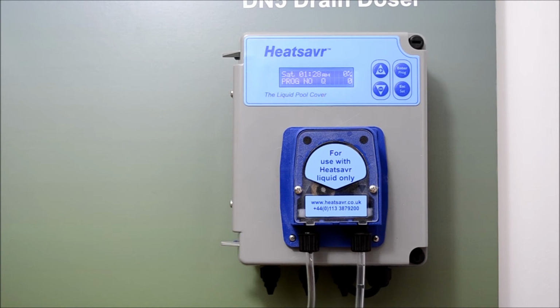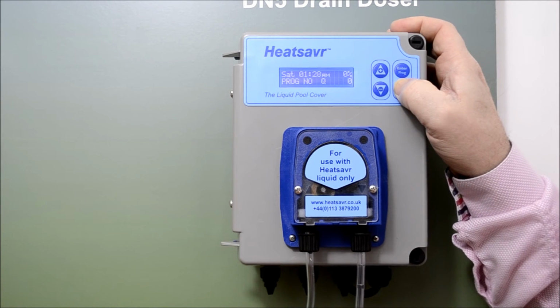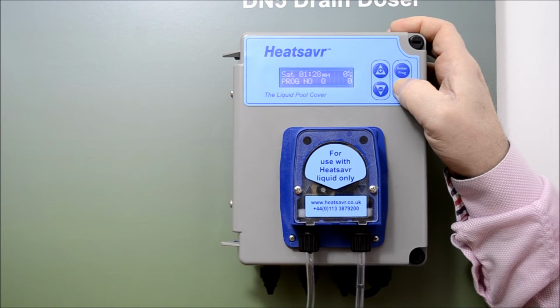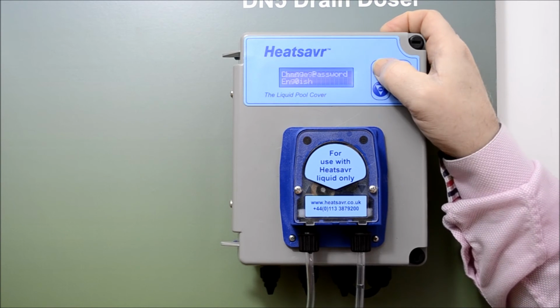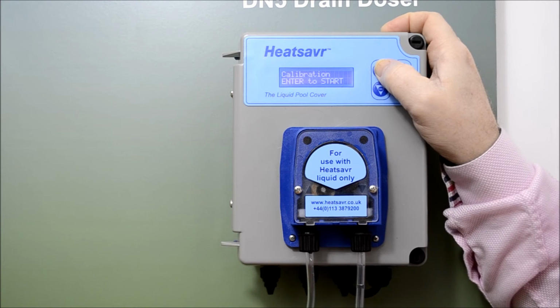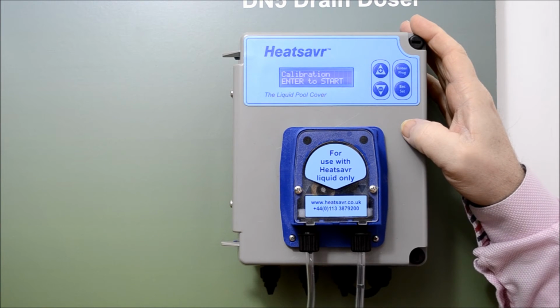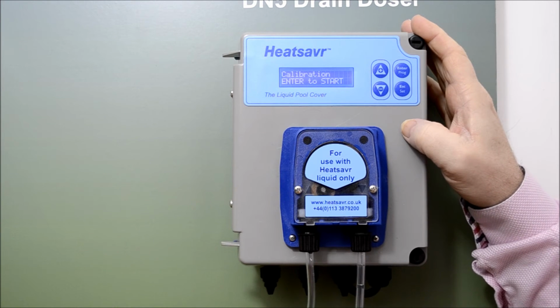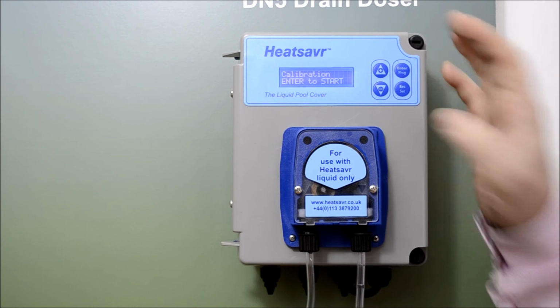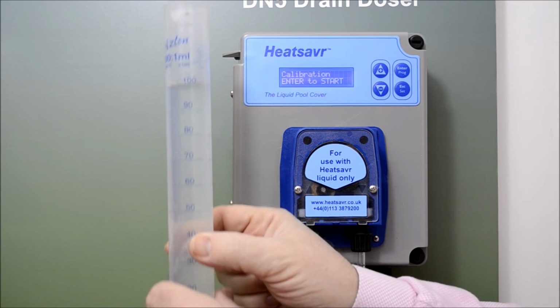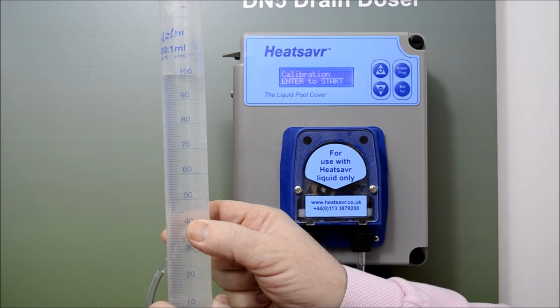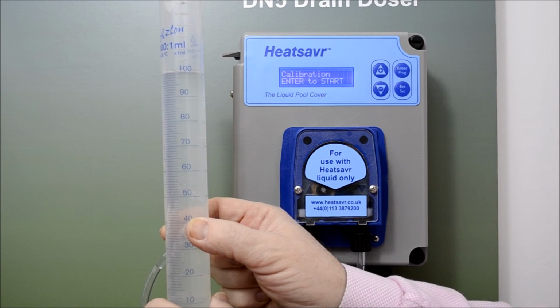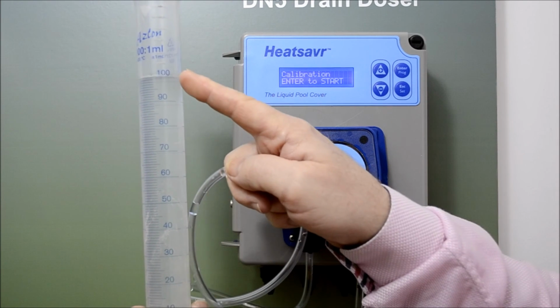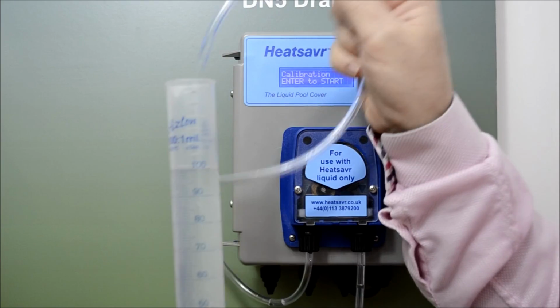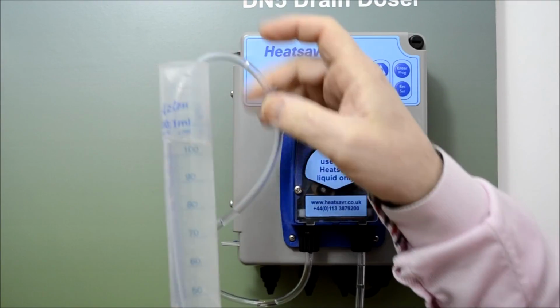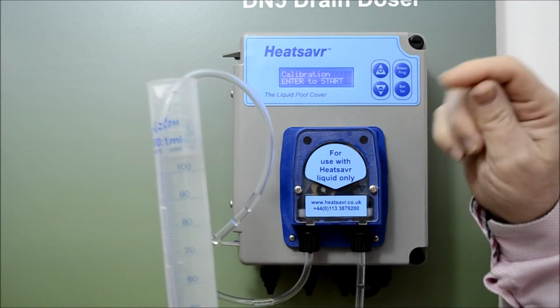To enter the calibration mode, press and hold the set button and scroll up to the calibration. Calibration is very important as it ensures accurate dosing. For this process you will need a graduated container of water. Generally 100 millilitres is sufficient. Take a note of how much water is in the container and then insert the suction tube. Press enter to start the calibration.